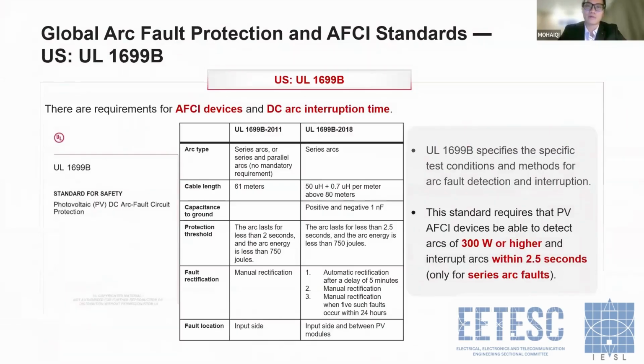Another one, for the United States, is UL 1699B. This one is very similar. It is also within 2.5 seconds, and arcs of 300 watts or higher should be interrupted within 2.5 seconds. But as we know, the standard is just the basic requirement of this technology. So if we want something more advanced, we had better have a different level of technology.